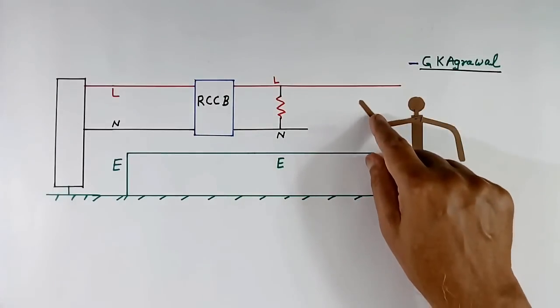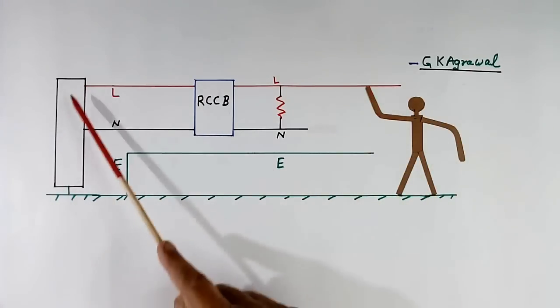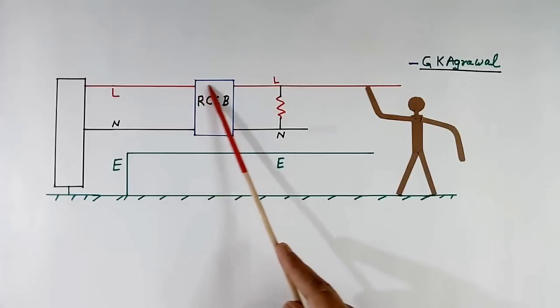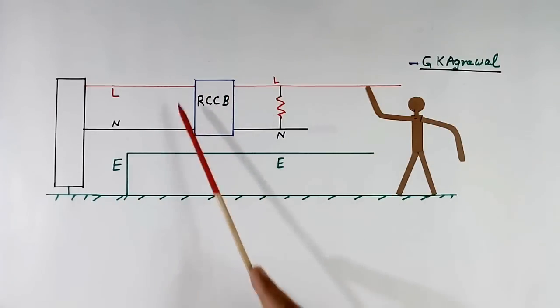Now suppose somebody touches line. Then current will flow like this, and we will get the shock. But because current what is going here is not coming back, it is coming back through earth, so this RCCB will trip and it will protect us.